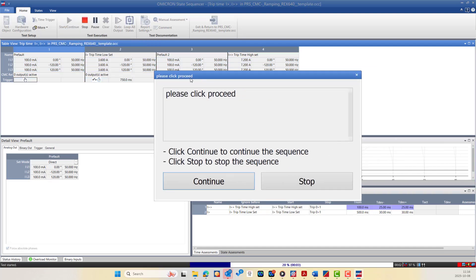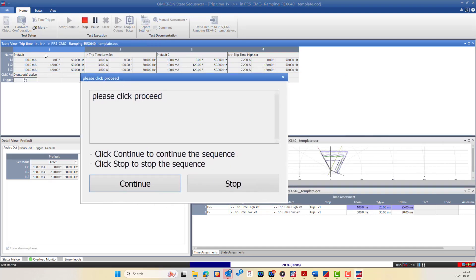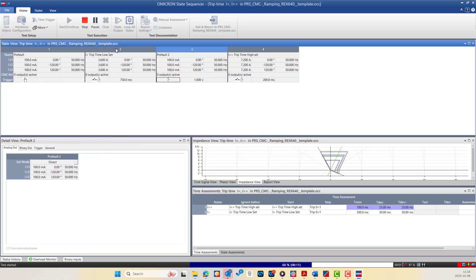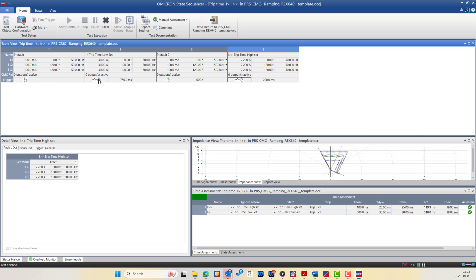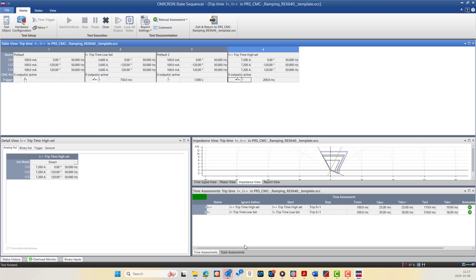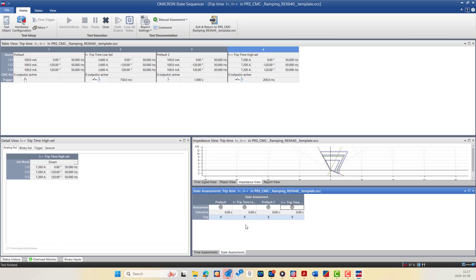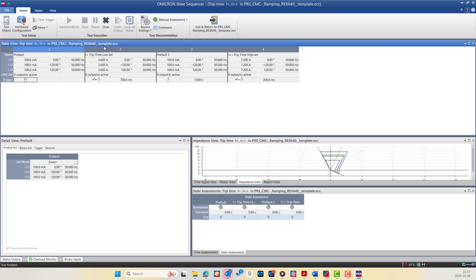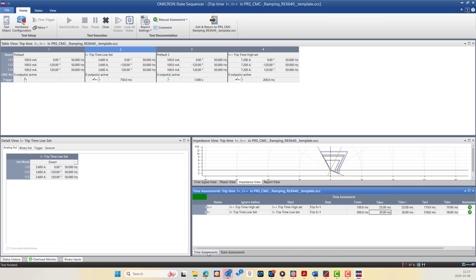Starting the test: state one is defined by user interaction so you click Continue. State two is defined by binary input or timeout, whichever occurs first. State three is the pre-fault default, and state four is defined by the binary input trip signal changing from zero to one. The actual results are then compared to the nominal parameter settings and assessed against the accepted tolerance per the relay technical specification. You can also define a State Assessment to measure the time between state one and state two, or between state two and state three.